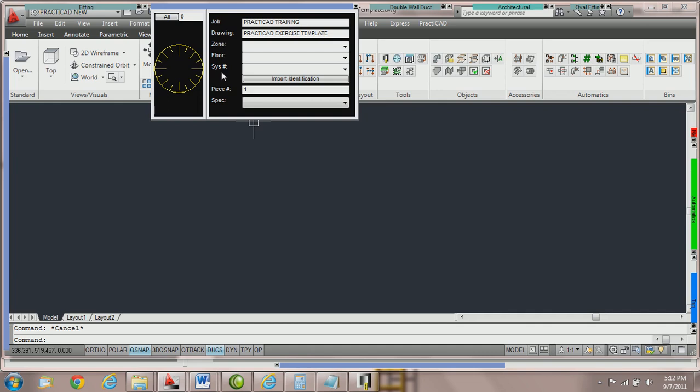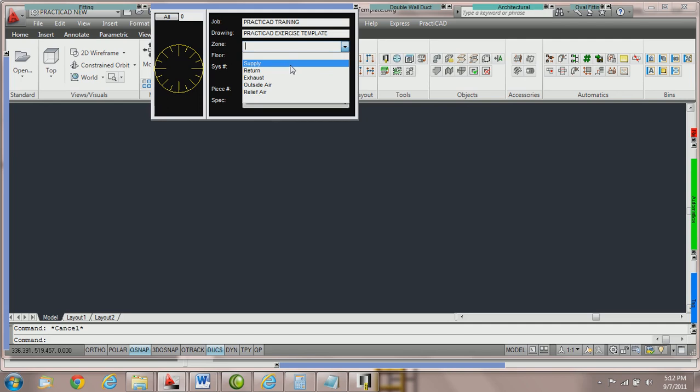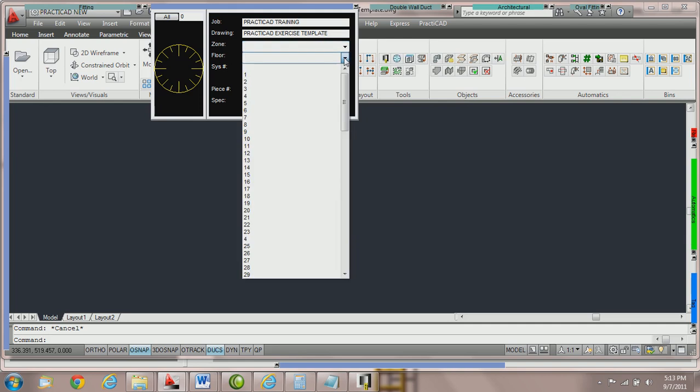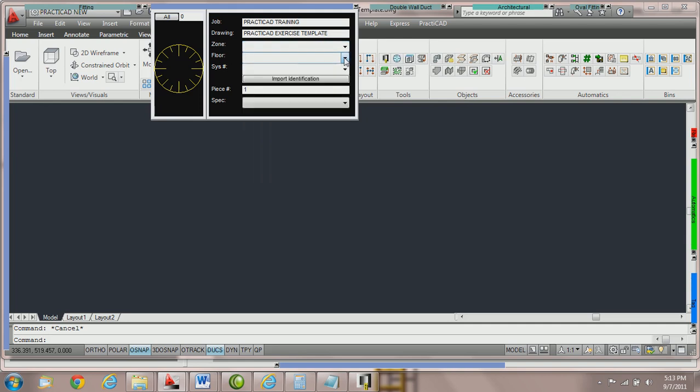These are just properties that can be reported in the system later. However, generally the zone is used for your supply, return, exhaust, relief, all the zones for a contractor. Floors are usually used for your floors from basement to ceiling, and system number is usually used to define a specific system like VAV1 or AHU1.